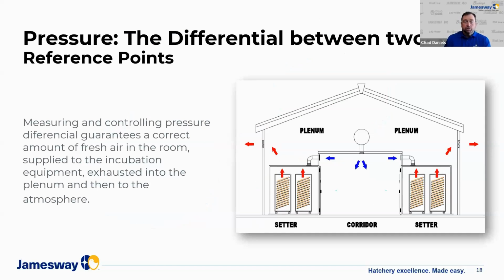Unlike temperature, where we can just measure one point, or humidity, where we just measure with one point, pressure has to be the differential between two reference points. So measuring and controlling pressure differential guarantees a correct amount of fresh air in the room, supplied to the incubation equipment, exhausted into the plenum, and then to the atmosphere, as we show in this figure. So when we talk about the fact that positive room pressure guarantees a correct amount of fresh air in the room, what that refers back to is we have all the incubation equipment consuming air from this room. And as long as we're able to maintain a positive pressure, that's confirming to us that we're providing enough fresh air to meet the machine demands.